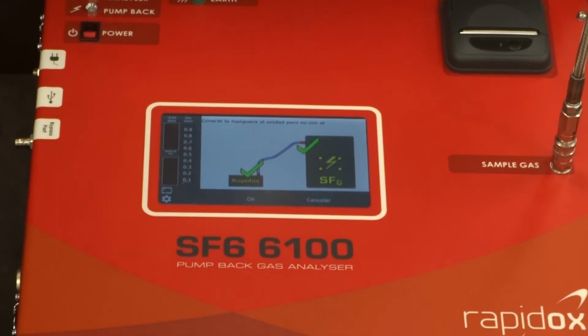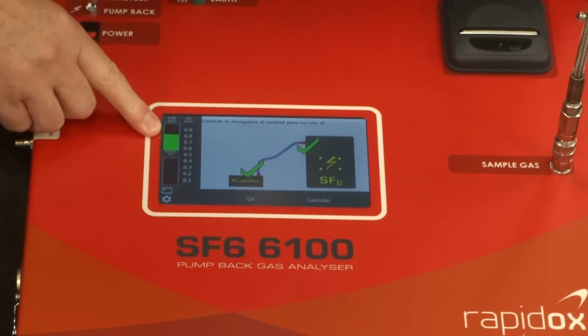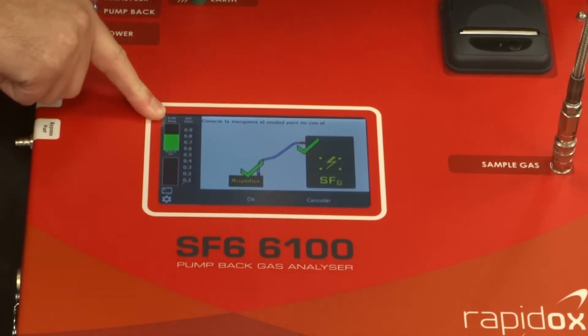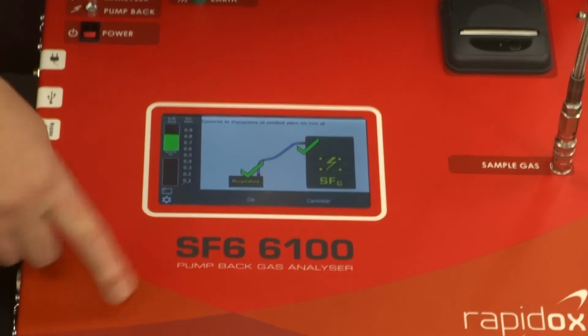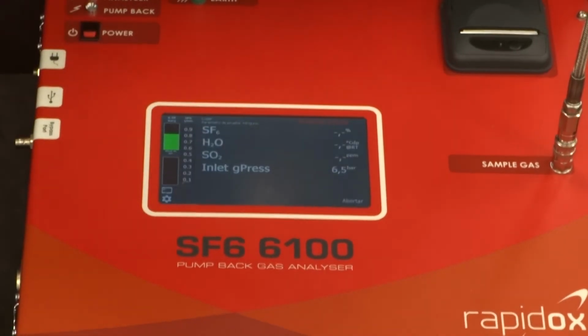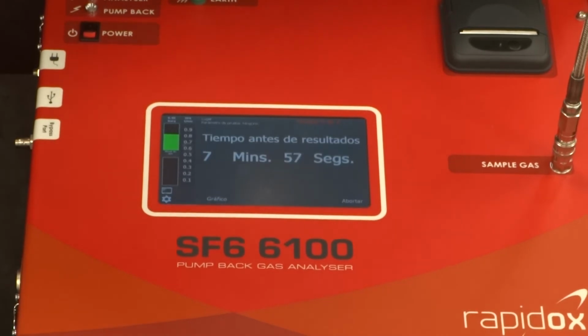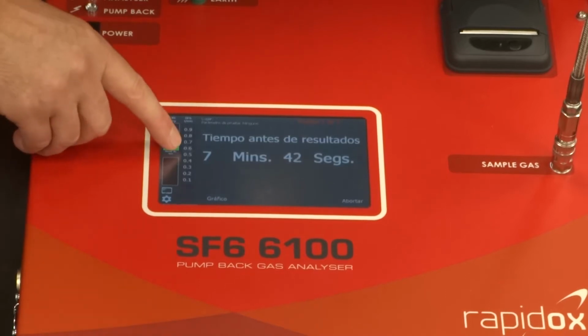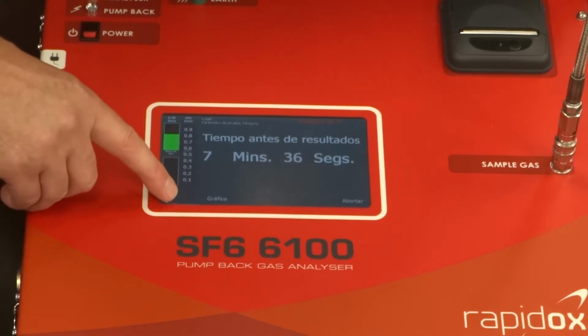So I'm now going to open my gas cylinder, and hopefully we will get some gas reading here. We can see that the pressure is rising, and this value here says it's 6.5 bar, which is fine. So all I do now is press OK, and a timer appears and the analyzer starts to measure the SF6. The SF6 is now travelling into the analyzer, and it is being placed into the storage bag inside the machine. Here you can see is the flow. The flow is approximately half a litre per minute. Here is the battery health.